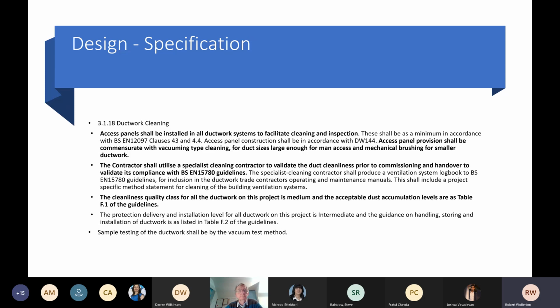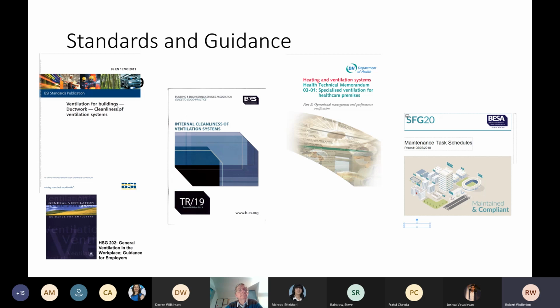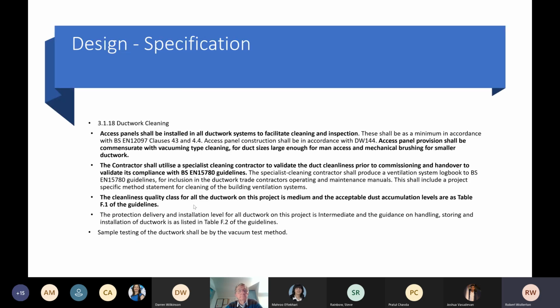So really they're also considering the size of access doors that need to be installed, because we sometimes go to projects and we find that access doors are too small to actually either facilitate an inspection or carry out ductwork cleaning. So I was talking earlier about the contractor shall utilise a specialist cleaning contractor to validate the duct cleanliness prior to commissioning and handover to validate its compliance with BS 15780 guidelines. So that goes back to what I was referring to here, the British Standard 2011. So that is now filtered out into specifications, which is fantastic as far as we're concerned. And I'll talk about the class of, here you can see it refers to medium. I'll come on to that a bit later on.